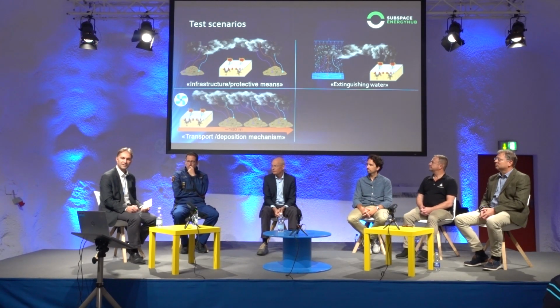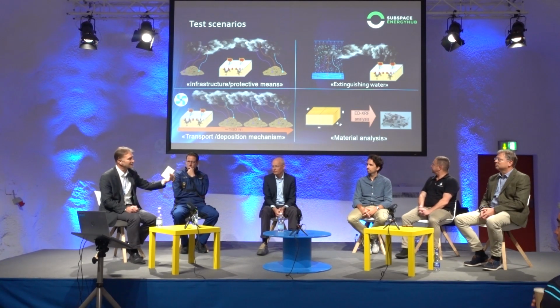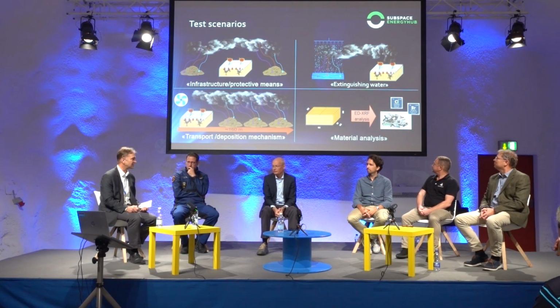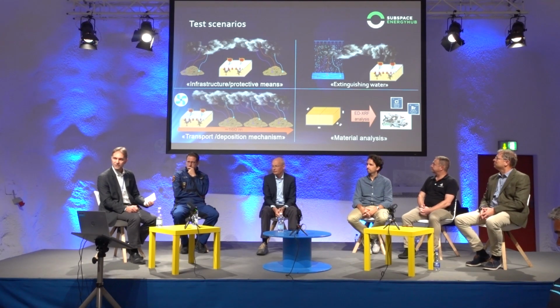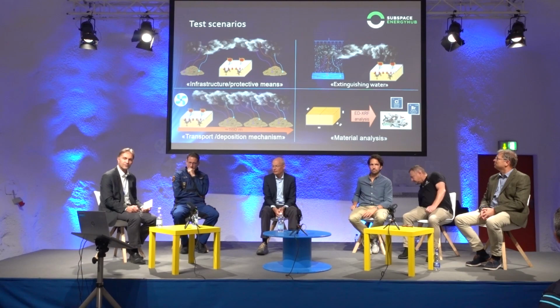lithium-ion battery, you cannot stop it. So it was put under cooling water, and the up-contamination of the cooling water was, of course, different than just the flushing, extinguishing water of the firefighters that you have. So we checked also what this means for our sewage channel system. This was analyzed. We checked the clothes of the firefighters. We were looking about the infrastructure itself, about cleaning possibilities after the test, how far materials, contaminations in a tunnel are transported, what are dilution effects based on ventilation. So a lot of topics.